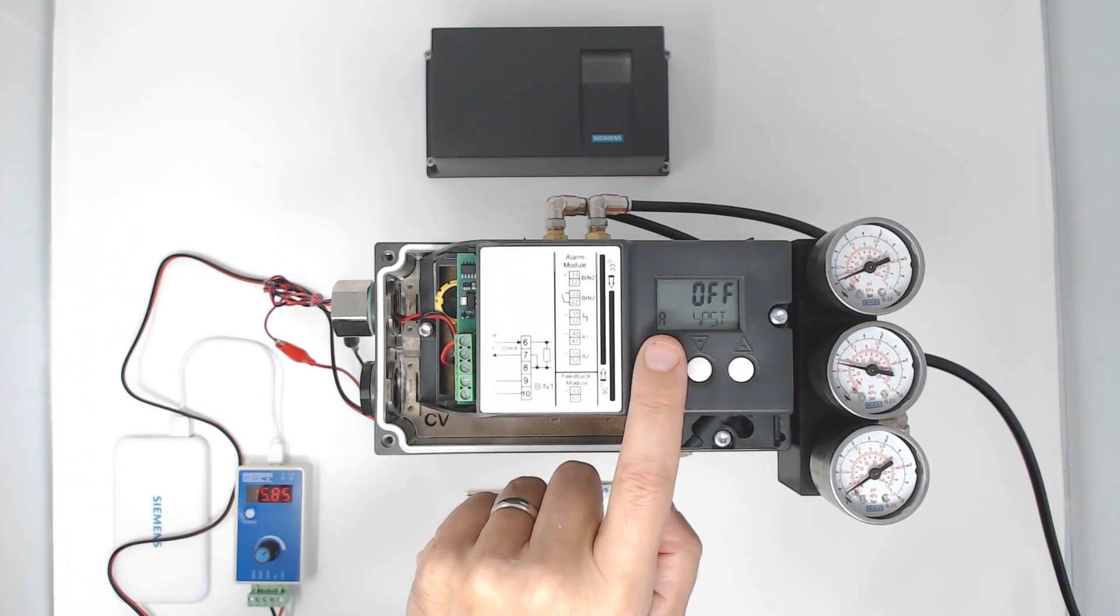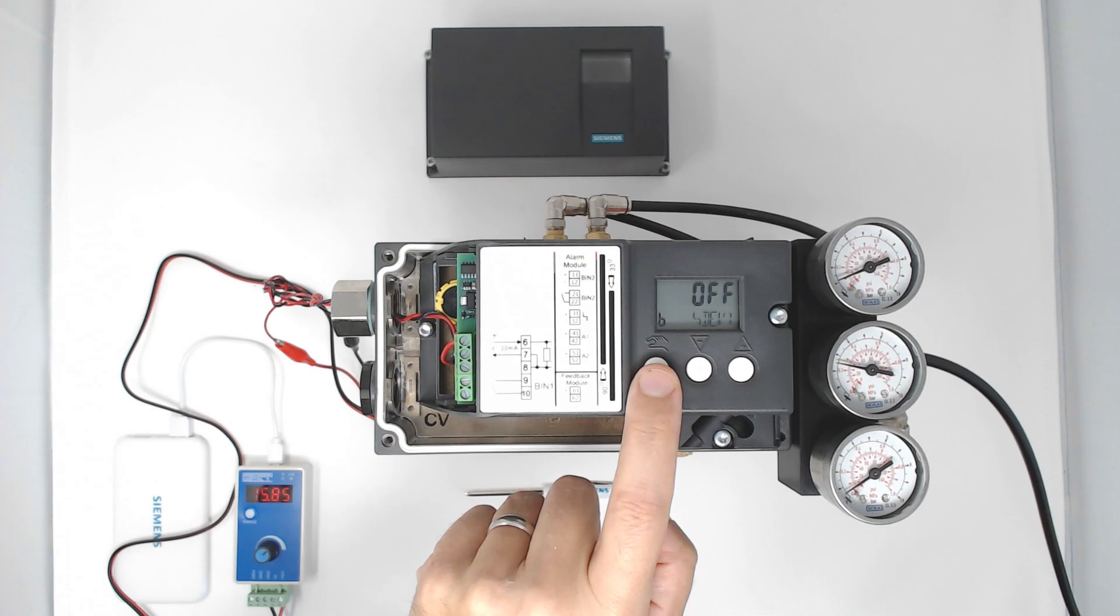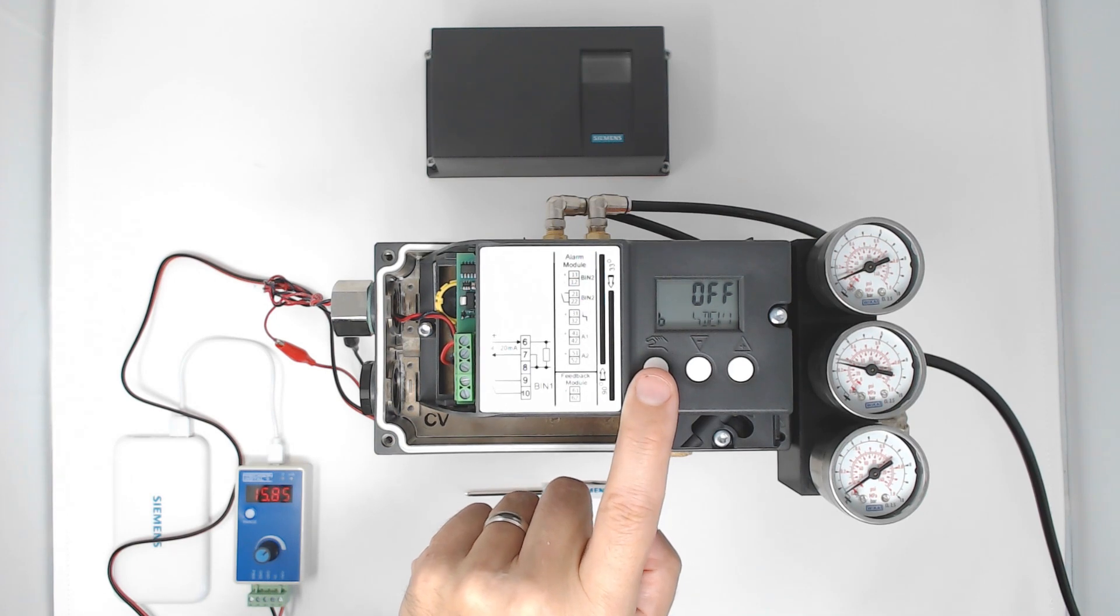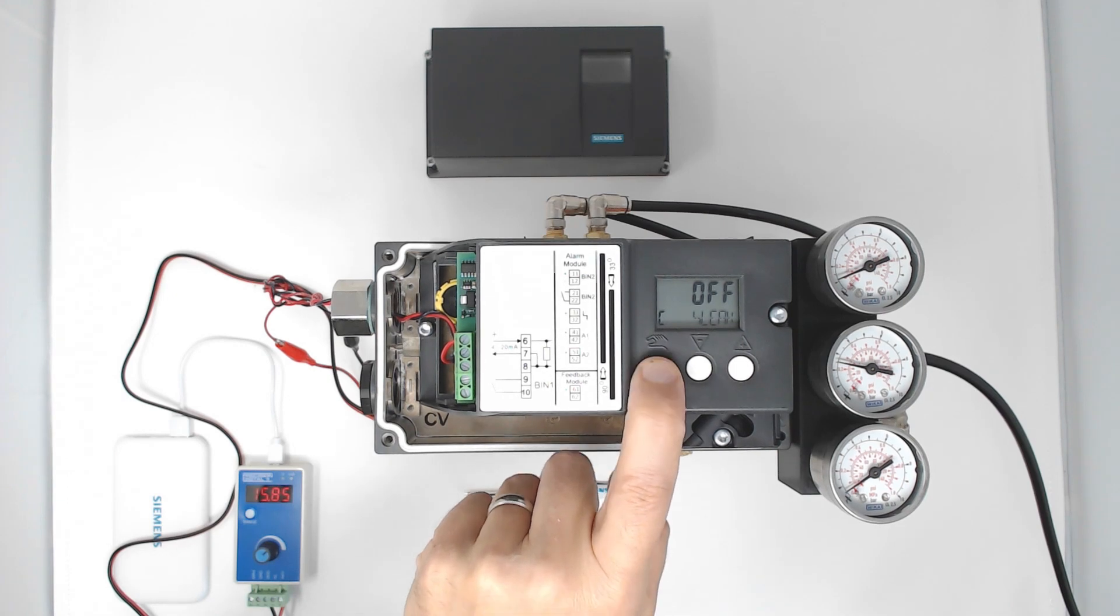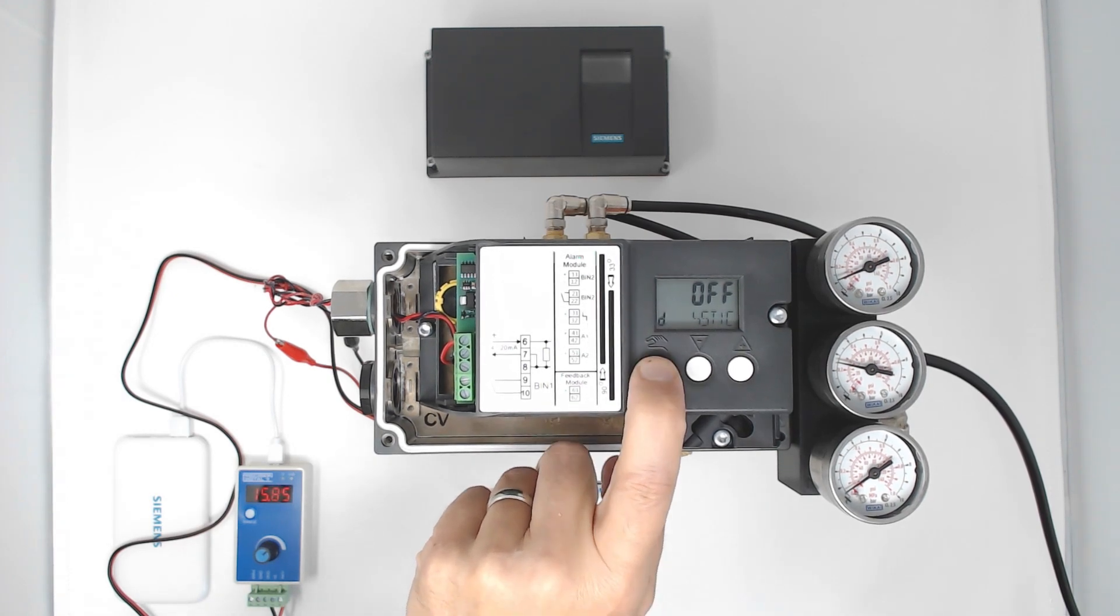Diagnostic A is the partial stroke test that you can perform. B is the deviation, whether the valve is deviating from the original initialized state. C is the leakage detection, D is the stiction, and E is the dead band.